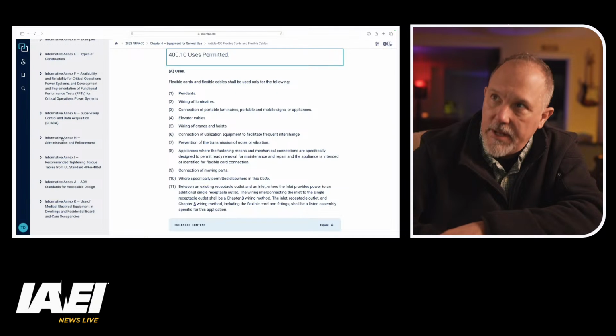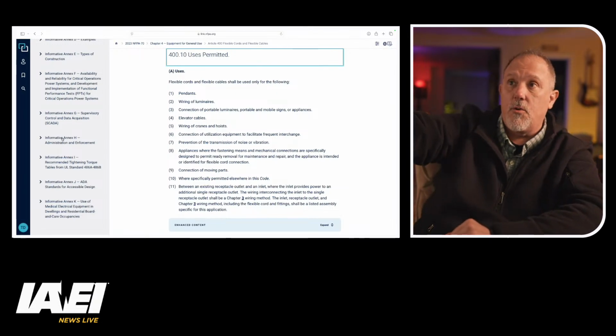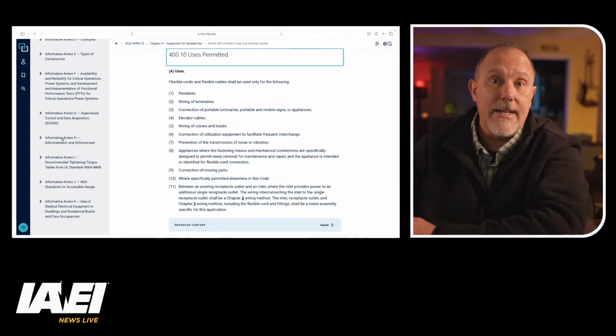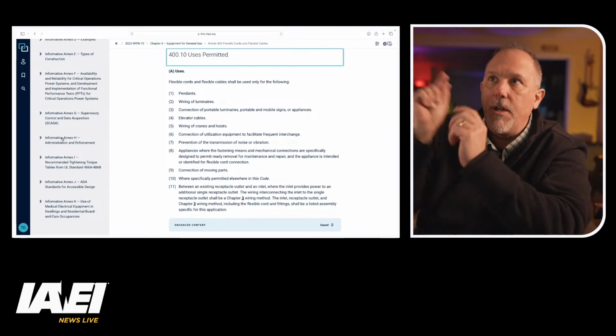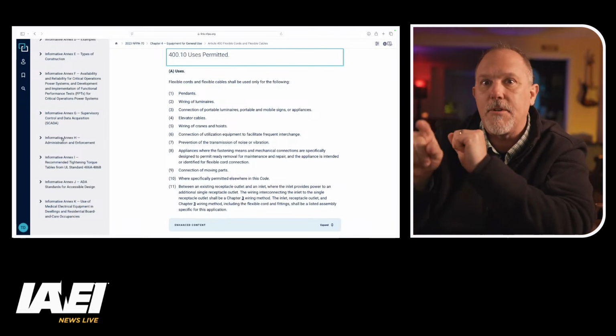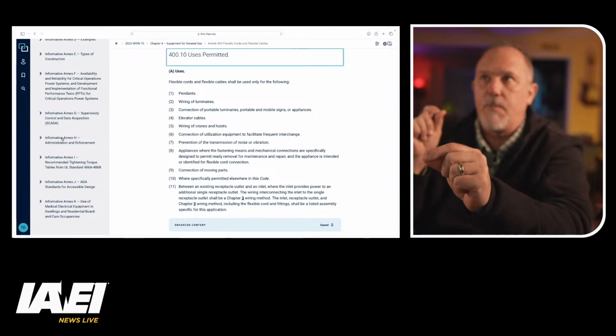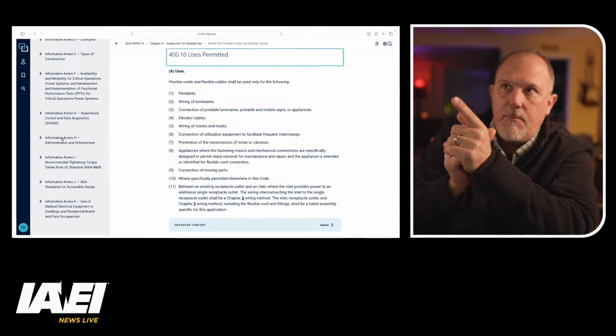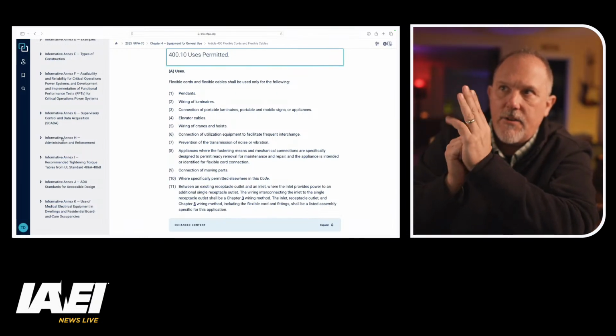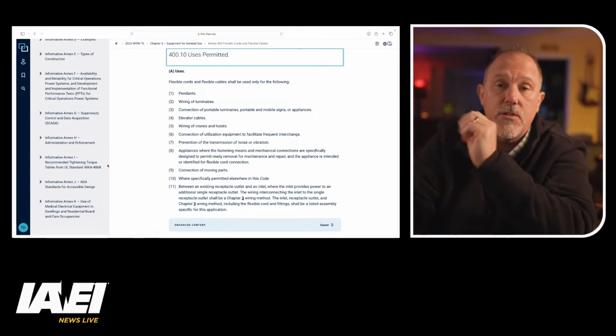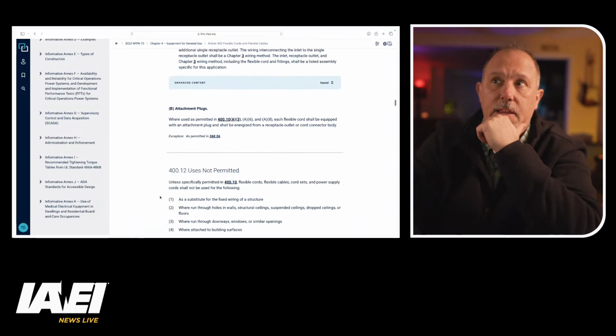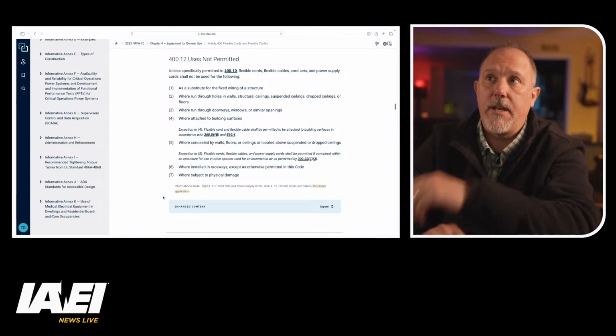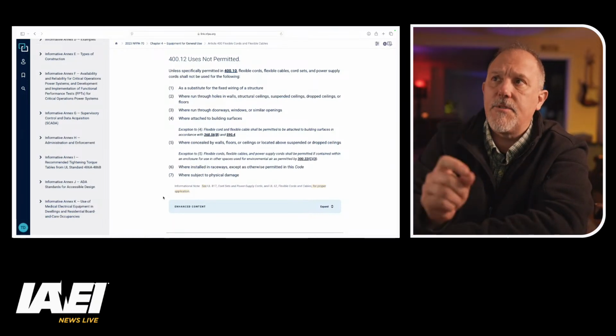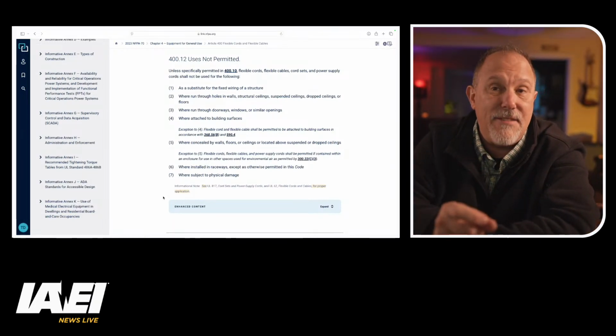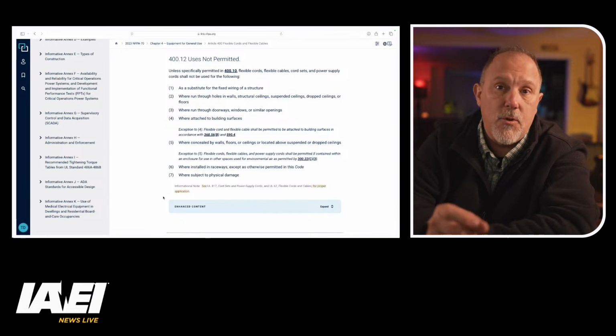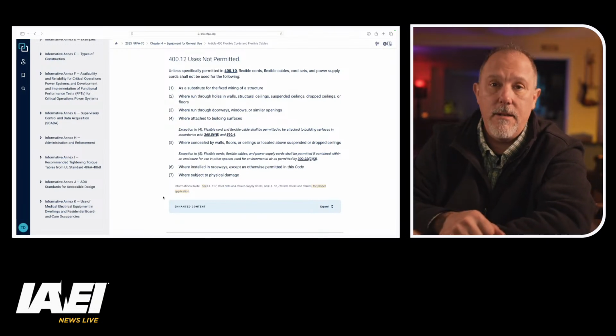400.10, uses permitted, tells you where you can use flexible cords — this helps you determine if what you're looking at fits this chapter from a cord perspective. You'd see it in pendants, luminaires, elevator cables, wiring, cranes, and hoists, so it's not just about a luminaire. Then there are uses not permitted, like as a substitute for fixed wiring.